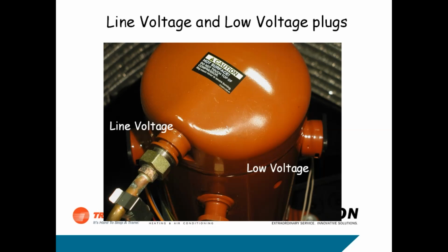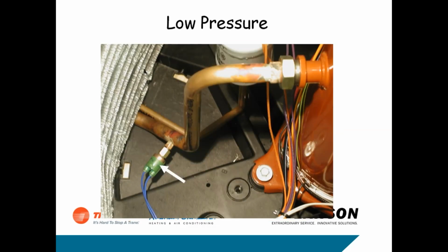I'd have to look at the ohm value for that solenoid. I'm not exactly sure what it is, but if it's open or shorted, it's bad. All right, we've got a low pressure switch. All of our units have low pressure switches on them. They don't have high pressure switches. The reason is, if you get to a high pressure situation, it's going to trip the internal relief valve, and that's going to throw hot gas on the internal temperature cutout, and it's going to shut the system down. But we do add low pressure switches to our units.